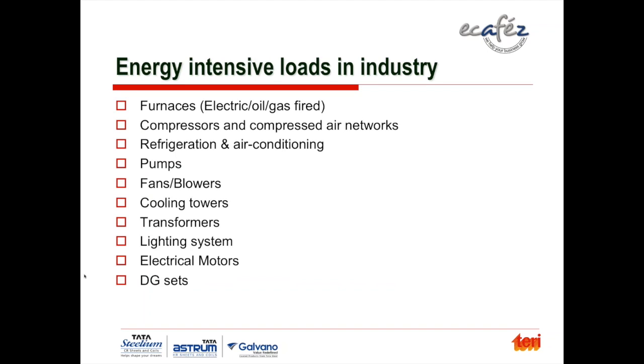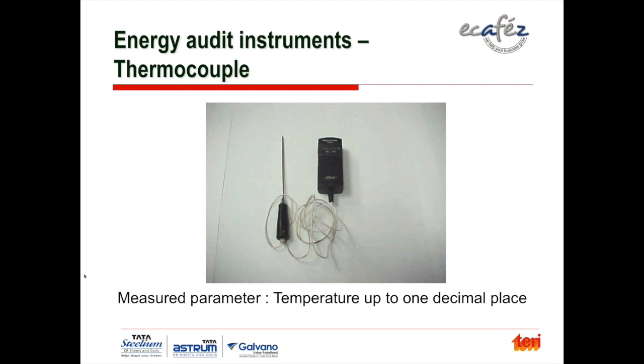Now, typically in an audit, the auditor looks at the following: furnaces in your plant, air compressor network, refrigeration and air conditioning system, pumps, fans, blowers, cooling towers, transformers, lighting, motors, DG sets, and so on. These are the major ones. Of course, it can be customized as per the plant requirement, but these are the major equipments typically audited by the auditor. And as I mentioned, energy auditing equipment plays a critical role in that. I'll just show you some of the energy auditing equipments which I used, to give you an idea of the kind of instrumentation which goes with a detailed audit.